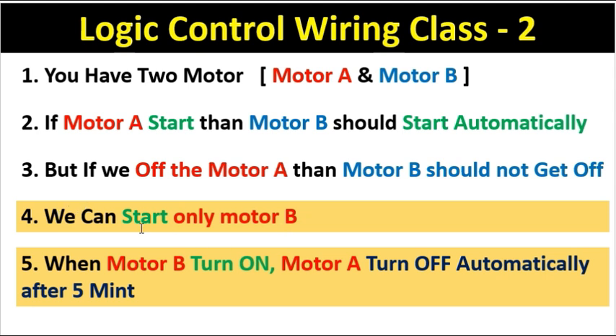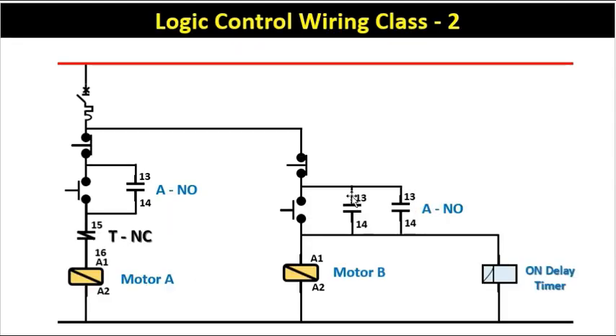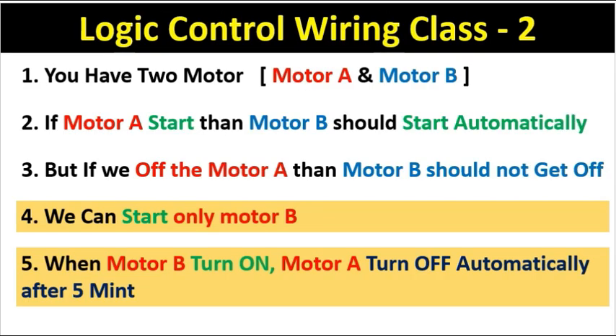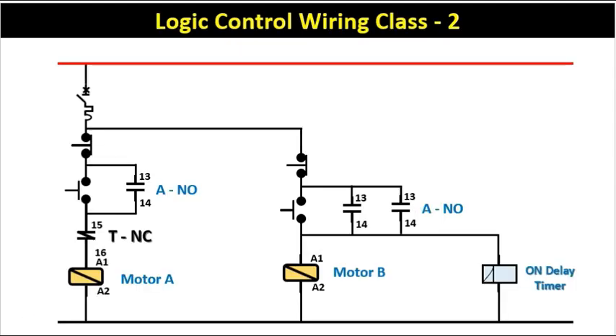Logic 4 asks to make a separate starter for motor B, which we already did. Logic 5 states that if motor B turns on, motor A should turn off automatically after 5 minutes. For this we used a timer, which operates with contactor B. On starting motor B, the countdown begins, and when it completes, the NC contact of the timer changes, turning off motor A automatically.